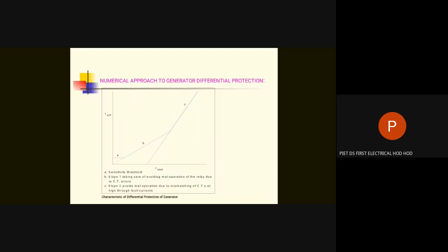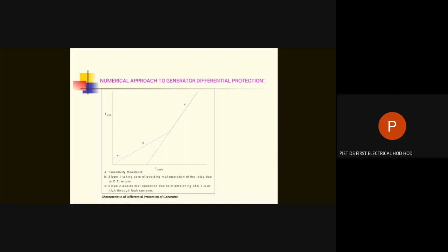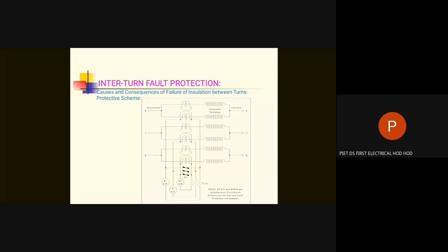The next slide is talking about the same thing. The next kind is inter-turn fault protection. Inter-turn fault is a fault between two turns of the same phase, because we have a double star winding. If there is a fault between two turns of the same phase, the differential protection we talked about cannot take care of it, because the current through CT1 and CT2, even if there is a fault, will be the same.